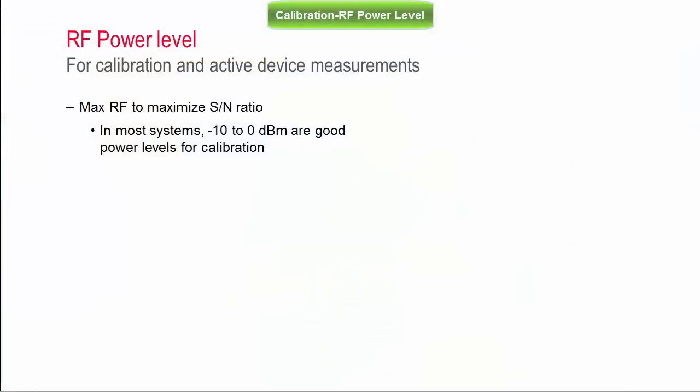The input power during calibration must be as high as possible to maximize the signal-to-noise ratio. Typically, minus 10 or 0 dBm are good RF power levels.